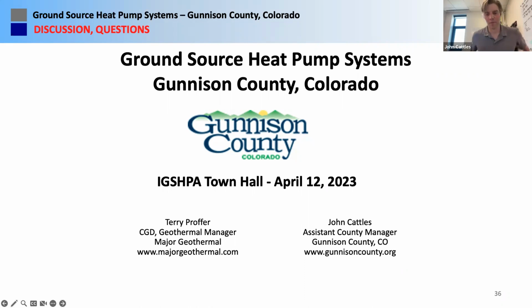We have several buildings with various systems, but from experience operating these, I can tell you that, for example, a building we have with a central boiler, a central chiller, a 4-pipe system, and VAVs, oftentimes I'll pull up to that building, especially at the shoulder season like now, and I'll see both the boilers and the chiller running at the same time. Consequently, what's happening with the controls to make that work and provide comfort to the occupants is a lot of gymnastics. There are controls trying to modulate VAVs, modulate valves for coils that are either cooling or heating throughout the building, and it never works exactly right.